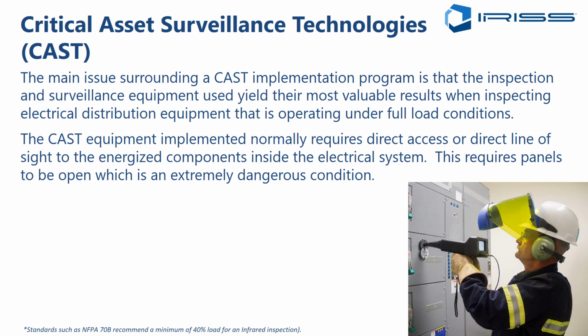Now, the main issue surrounding the implementation of a CAST program is that the inspection and surveillance equipment normally yield their most valuable results when inspecting under full load conditions. In fact, NFPA 70B recommends a minimum of 40% load when we're doing an infrared inspection. Now, CAST equipment input normally requires direct access or direct line of sight to energised components in the electrical systems, which requires either panels to be open, or we need to shut down. So we don't want to shut down because we want to inspect under load, and we don't want to open the panels because we recognise that's a very, very dangerous condition.